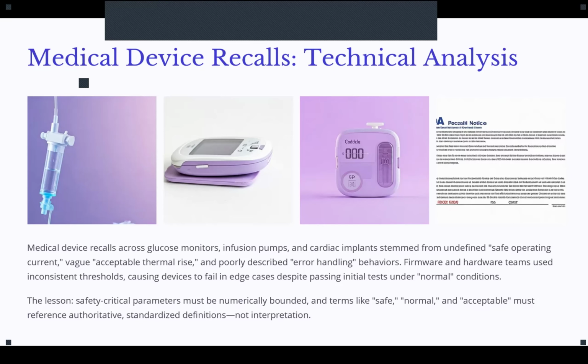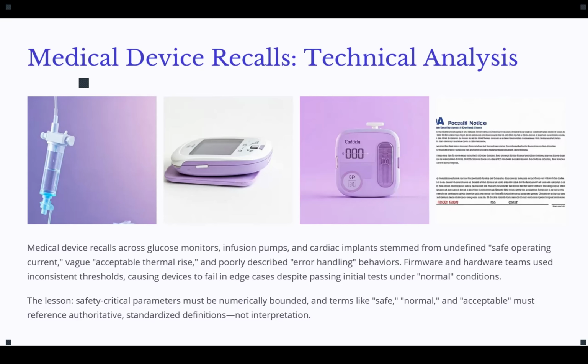Example of the failure: safe operating current, that definition left undefined across software and hardware teams. That ambiguity creates problems, like in the blood glucose monitoring, or acceptable thermal rise, it was not quantified in clear standard units, which introduced a malfunction in our circuit and system.